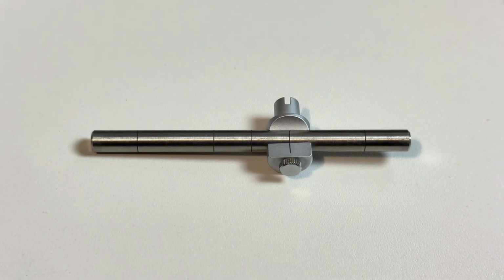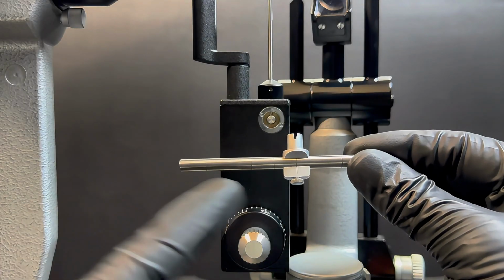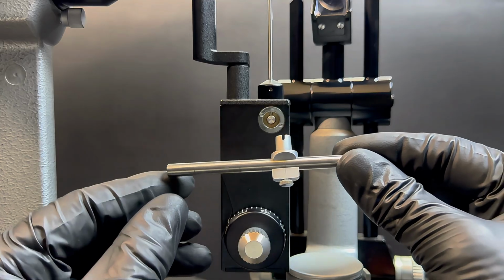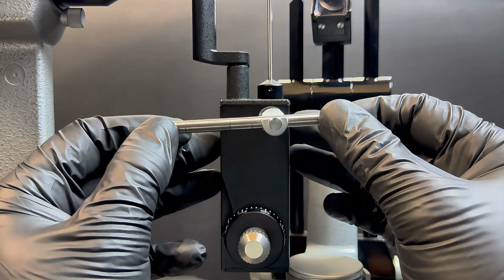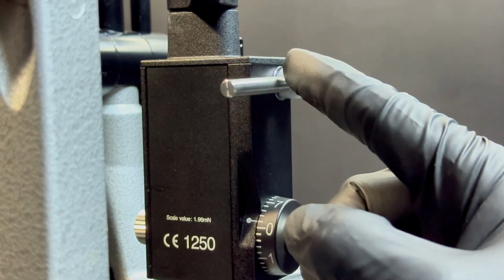We'll now check calibration at the 2 setting. Set and secure the weight at the 2 position on the calibration bar. Align the cutout on the calibration bar with the key on the tonometer, then slide the bar straight on until fully seated, with the longer end pointing toward the examiner.